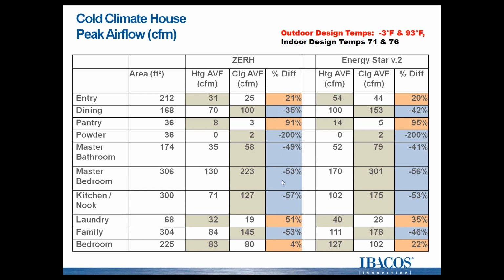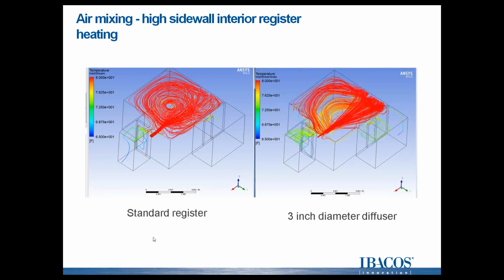And so the other challenge that we're faced with at lower and lower airflows is mixing the air both in the zone and around the house. And here's just a little bit of CFD modeling we've done. In the standard register case, you can see that there is some mixing, but what actually is happening here is you have a lot more stratification. And we've actually looked at a case with a much smaller register that results in a higher outlet velocity, and you can see that there is somewhat better mixing down into the room in that case. So same CFM, but you get better mixing. So you have to be very careful with your design in order to mix the space.